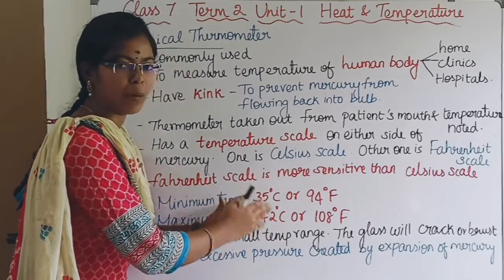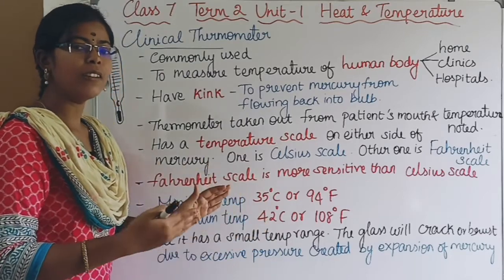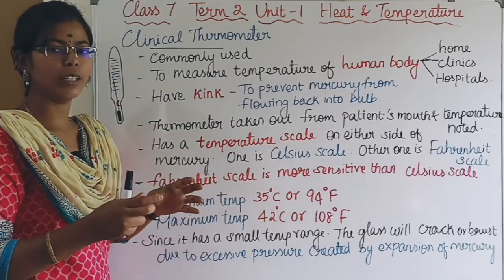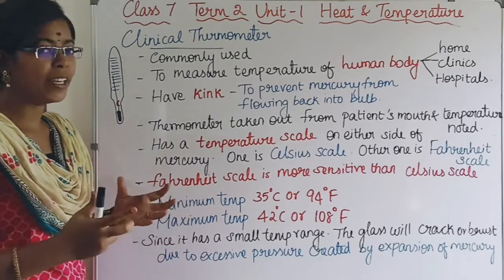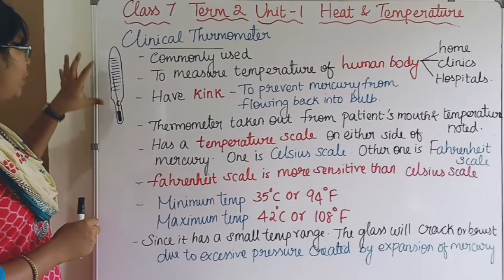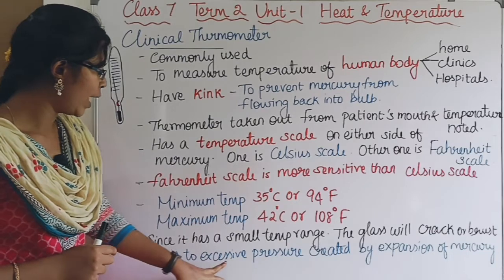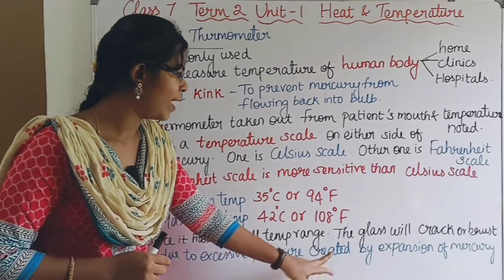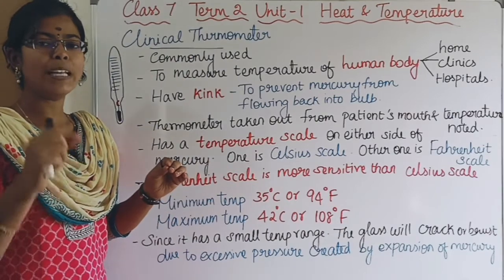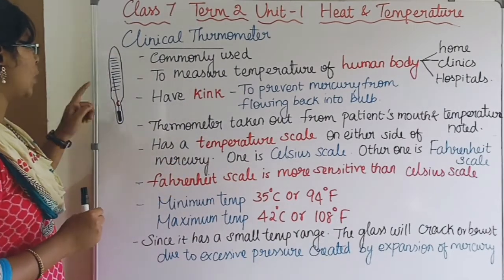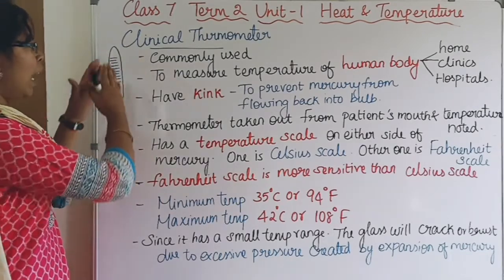In this temperature range, we use the clinical thermometer for the human body. Warning: do not place the clinical thermometer in hot water, as the temperature will cause the glass to break. This is due to the excessive pressure created by the expansion of mercury. When heat is applied, the liquid expands and the glass breaks.